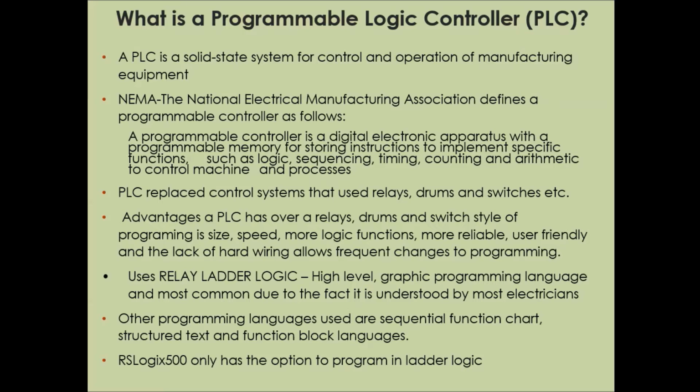Relay ladder logic. It's a high-level graphic programming language and is most common in PLC languages due to the fact it's understood by most electricians because they already know relays. Other programming languages used are sequential function charts, structured text, and function block languages. RSLogix500 only has the option to program in ladder logic. And RSLogix500 would only be used to program a certain series of Allen-Bradley PLCs.